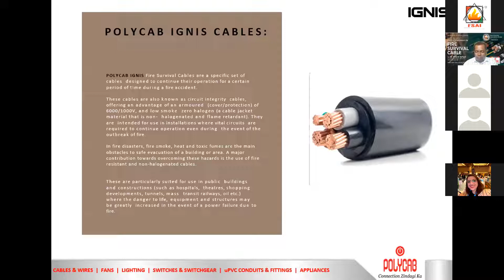What are the characteristics and advantages of these cables? Enhanced fire resistance protects the electrical circuit from fire. Taking reference from technologies present world over, there is a maximum rating available of 950 degrees centigrade for 3 hours, which is the calculated community decision that 3 hours is sufficient to evacuate the tallest building in New York.